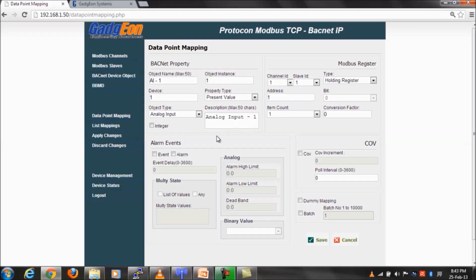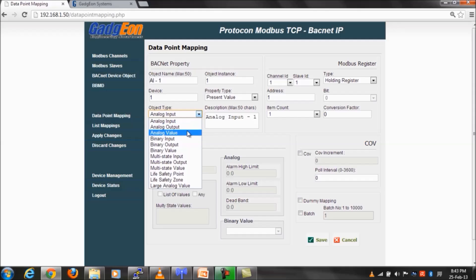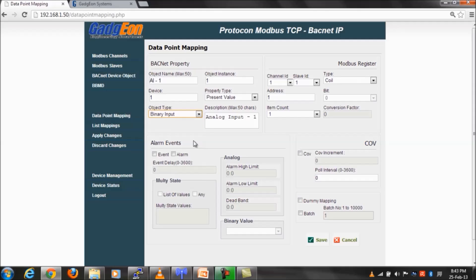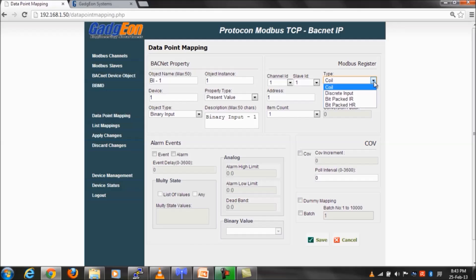Modbus input register or holding register can be mapped to binary input or value in a granularity of bits. Input or holding register is 16-bit, and each of these 16 bits can be mapped to binary input or binary value object type.